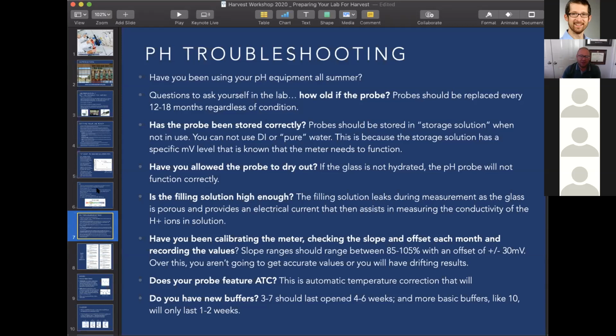Do you have an automatic temperature correction probe? Looking at that is really important, because we deal with a lot of different things and turbidities but more importantly, different temperatures with your pH readings, and you want to make sure that your temperature is adjusted for the pH reading. There are these little temperature probes that will go in at the same time as you put your pH probe in.